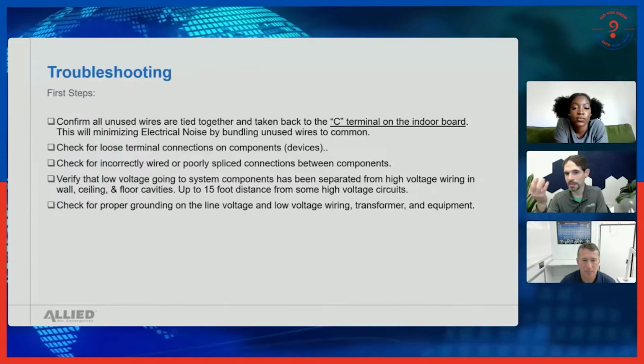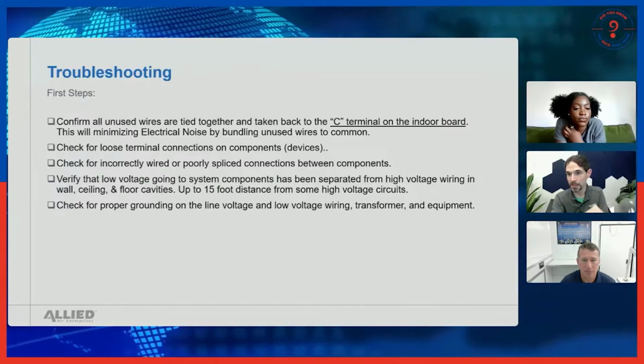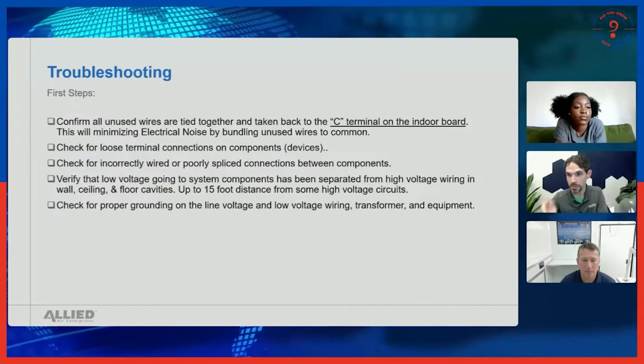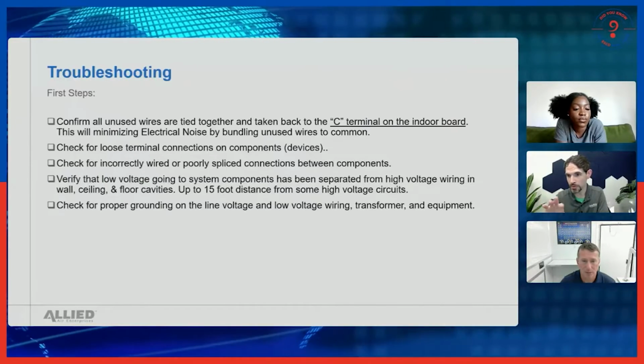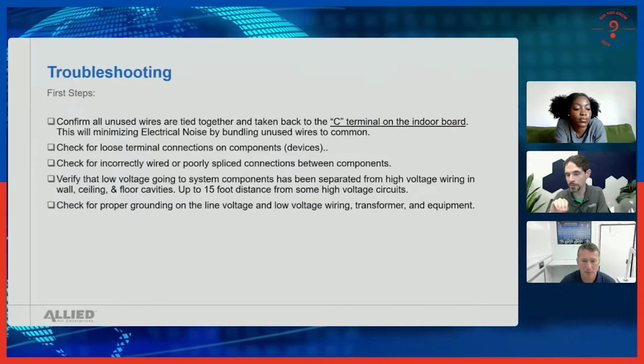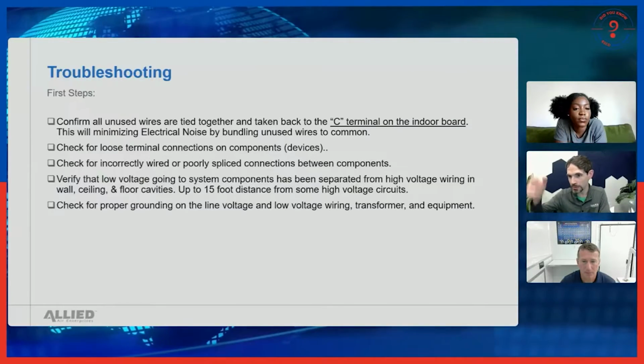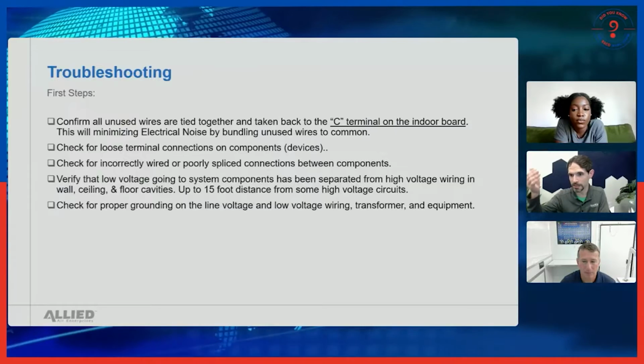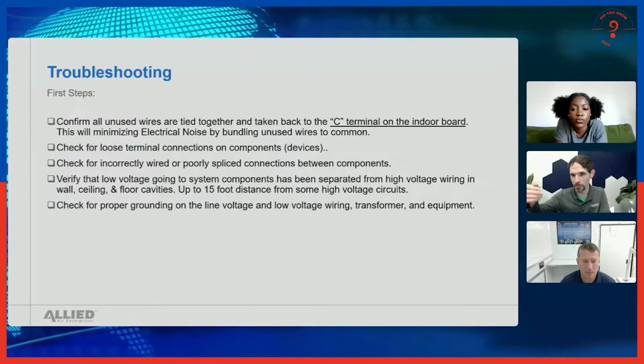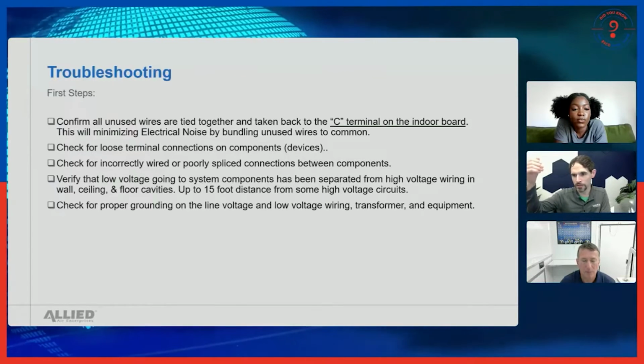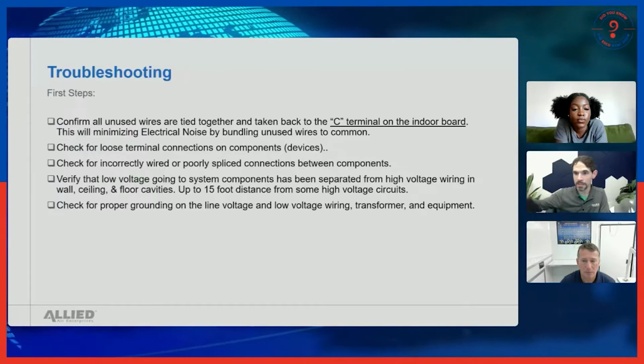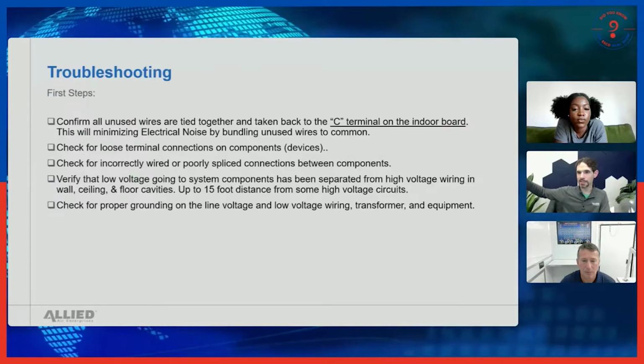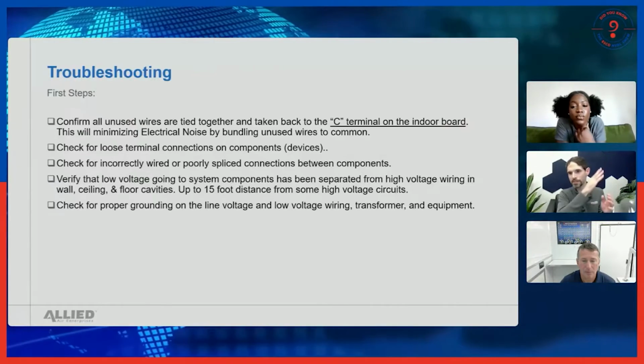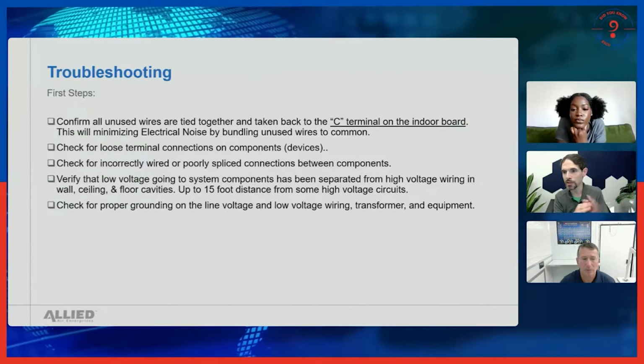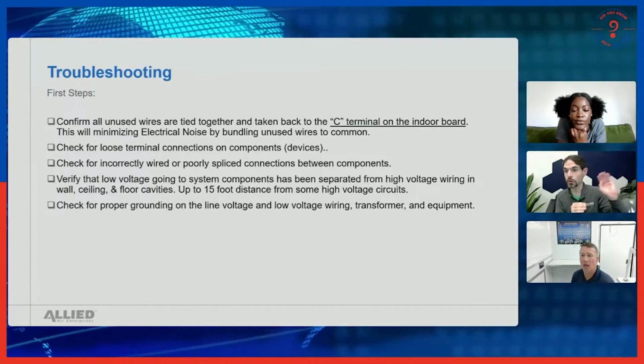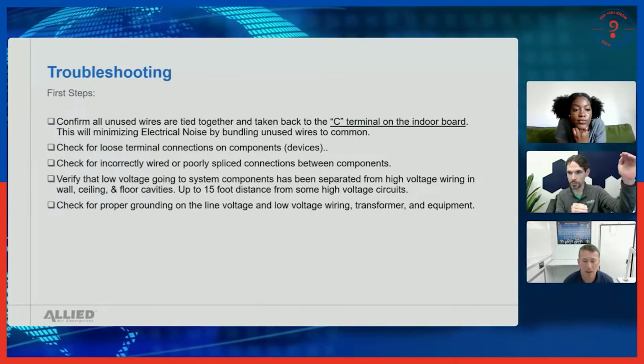So what we say is, take your extras and land them back on the C, the terminal strip of the equipment. We're talking about a 4-wire set for communicating, but on the equipment there's still a standard terminal: your Y1, your W's, your C's, your R. Take the excess out of the path we're communicating along and drop that to ground in a solid set point.